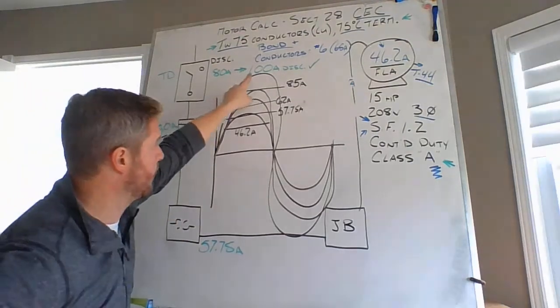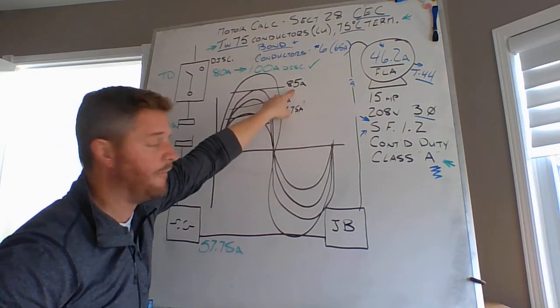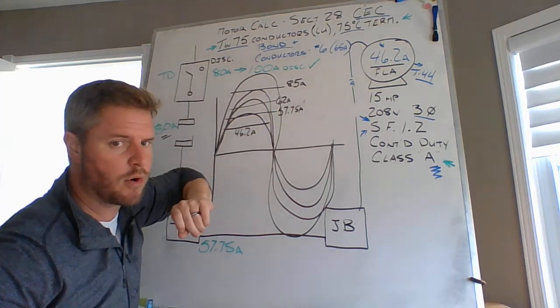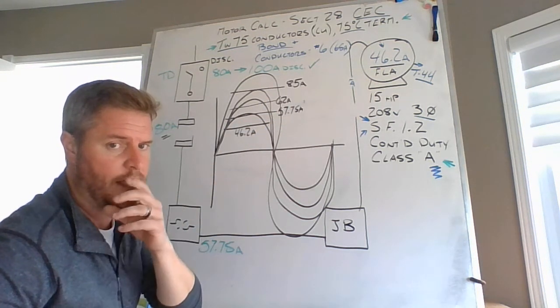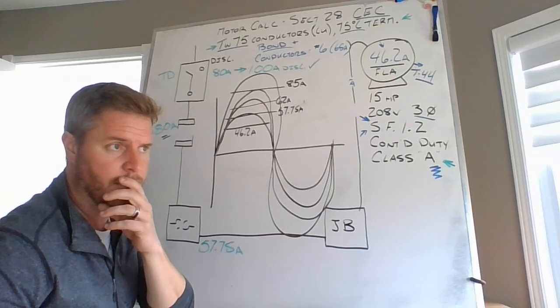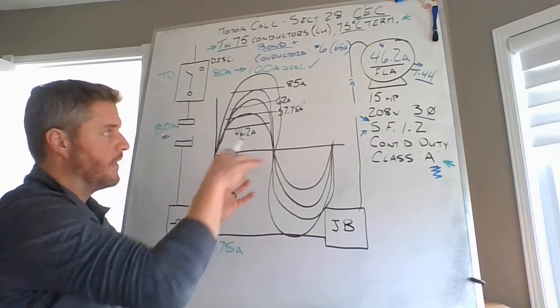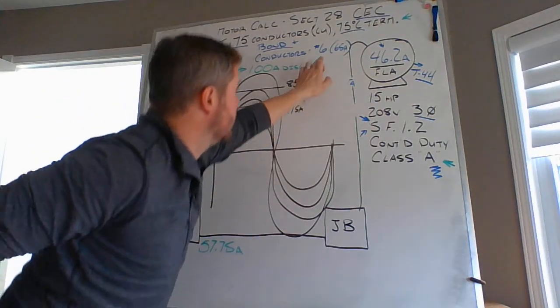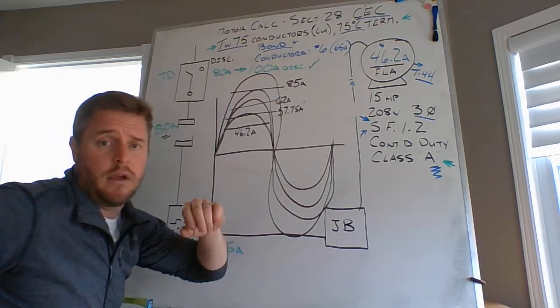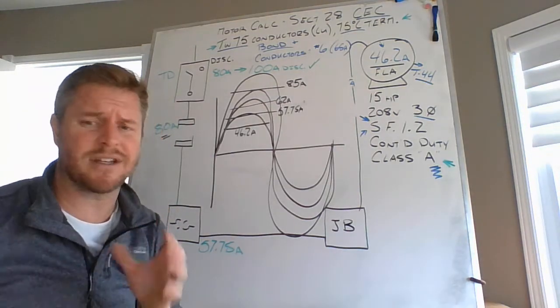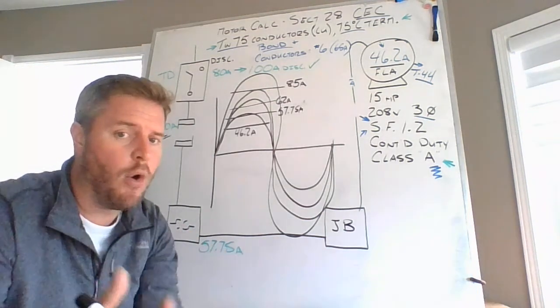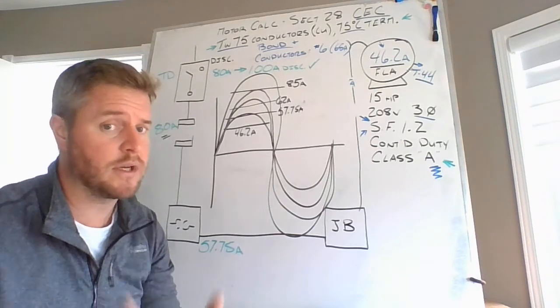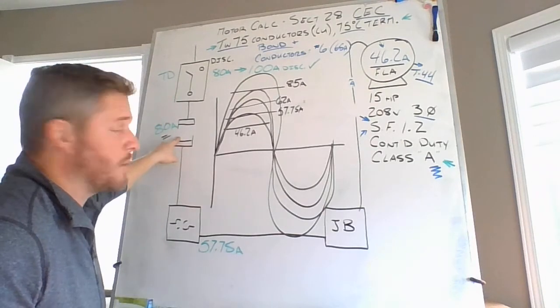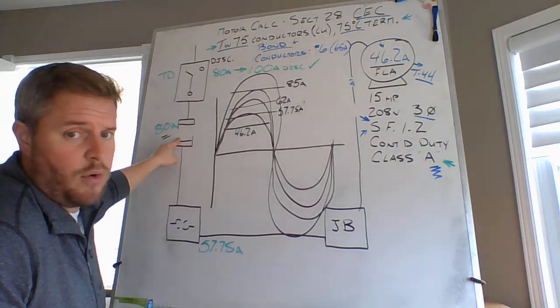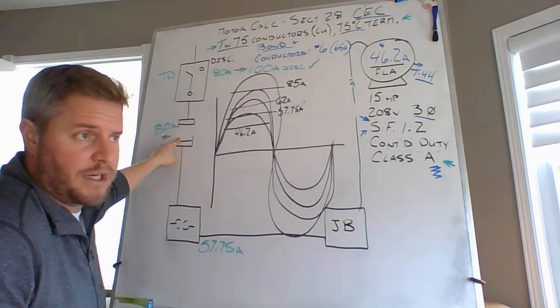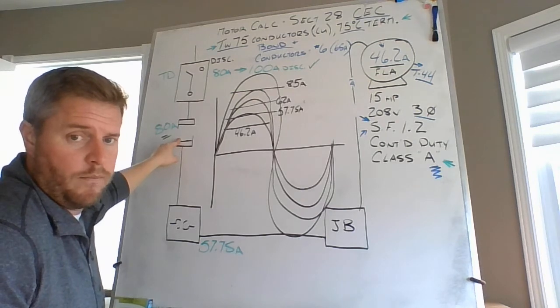That's the inrush current thing about a motor. It might spike up to 85 amps. Maybe. Every single motor is different. That's okay for just a couple of seconds for that motor to get up to speed, because realistically you installed number 6 conductors. It'll handle that inrush current as long as it doesn't persist or keep increasing in current, because then your overcurrent protection comes into play. It says, no way, pal. You're at 85 amps for 20 seconds. You're not going to handle that. I'm out. And I open.